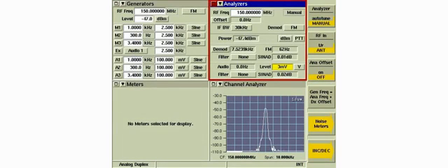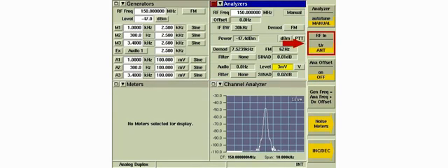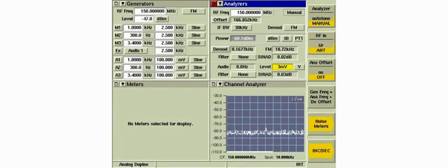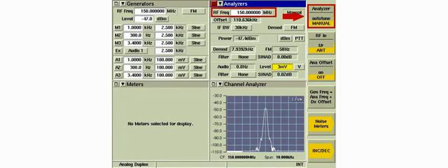The analyzer's tile contains the RF receiver and DMOD functions of the instrument. The RF In soft key selects the TR or the antenna connector as the receiver input. The receive frequency can be either found using the auto-tune function or manually entered. The selectivity of the receiver is set by the IF bandwidth filter selection.